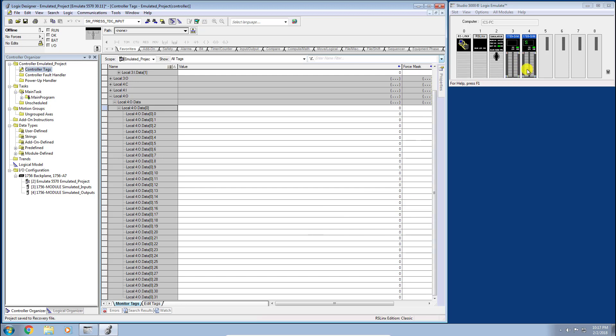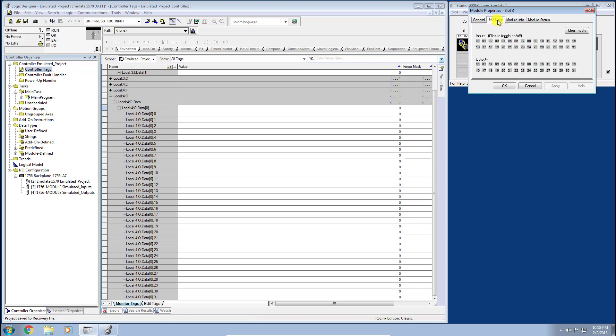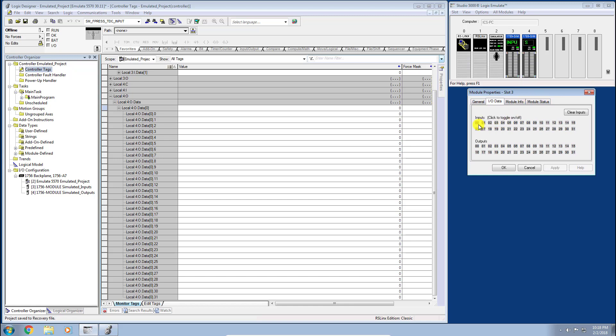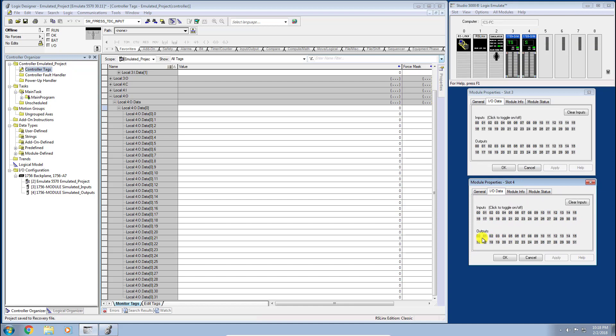One more thing to point out about the Logix Emulate: if you right-click the input module and go to Properties, there's an IO Data tab. Here you can toggle inputs on and off just as if they were limit switches in the field being activated — a nice quick feature for testing. You can also see output status in real time as your program logic drives the outputs. We'll be making use of these module property toggles in subsequent videos.